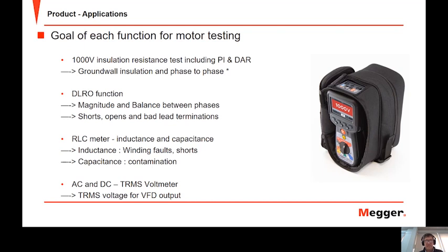The capacitance test can be used to find contamination in the winding to earth. But again, this has to be a trending test. We don't necessarily know what is a good or bad value, so we need to really trend that over time. And the voltmeter allows us to measure the voltage in the circuit or even between phases, of course. But we also have the true RMS voltage measurement for measuring the output of an inverter drive, a VFD. Plus, we have that all-important rotation direction of the power supply, which will help us ensure that the motor rotates in the correct direction when used with the motor direction test.